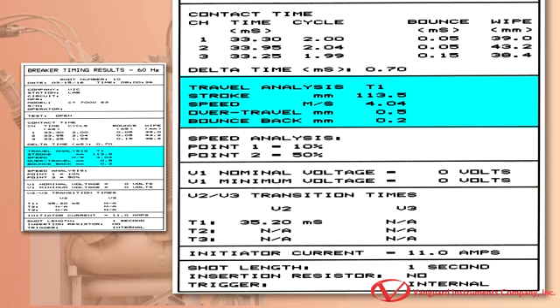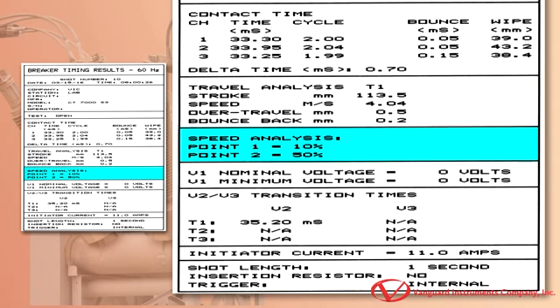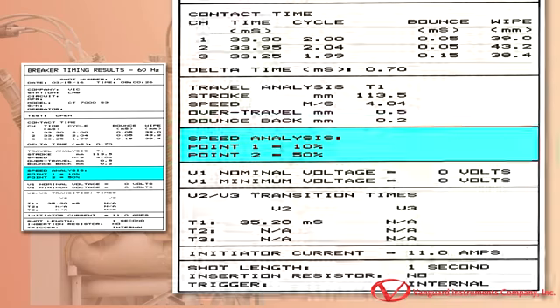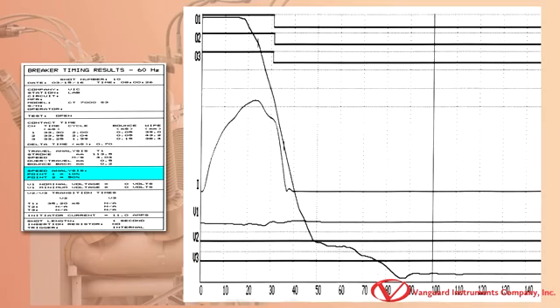The travel analysis for transducer 1 is shown here. The analysis comprises the breaker stroke, contact velocity, contact over travel, and contact bounce back. They can be displayed in either English or metric units. In order for the CT7000S3 to calculate the contact velocity through the arc zone, the user must first define the 2 points on the travel curve. The 2 analysis points to be used are defined as AP1 and AP2.